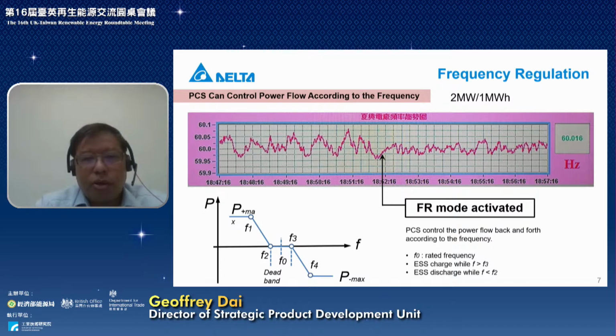Taipower tried to figure out a solution to improve the blackout situation. Here's a chart about the frequency over Kinmen Island. On the left-hand side, you can see the frequency fluctuation is quite high, almost plus minus 0.05 hertz. We built our system, 2 megawatts and 1 megawatt hour - not big, just a small energy storage system - and we enabled frequency regulation mode, activated in the middle of the chart.